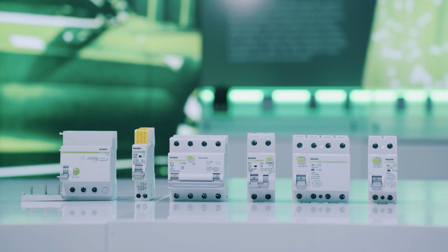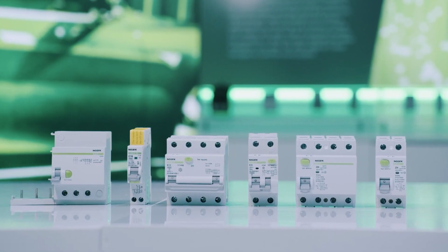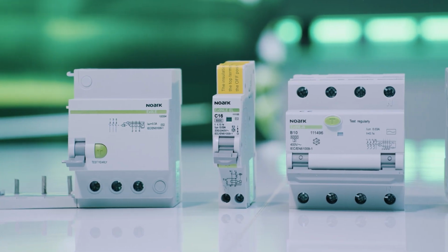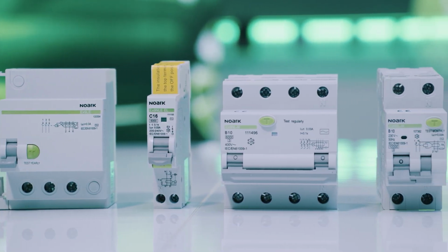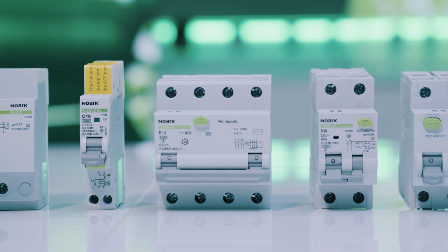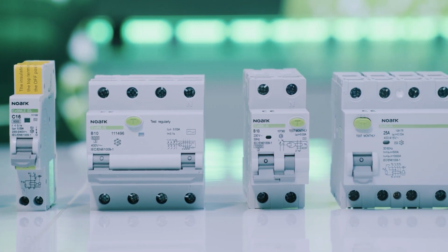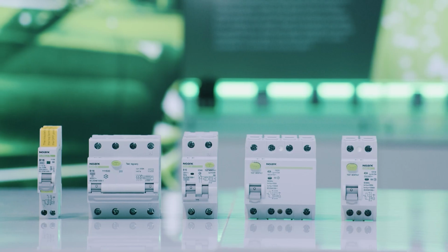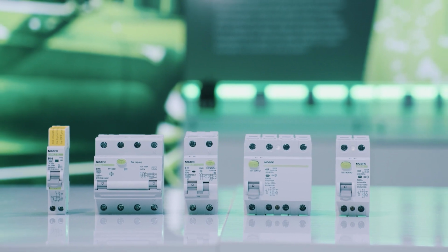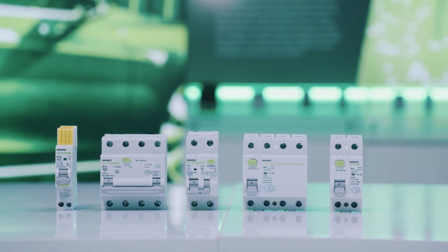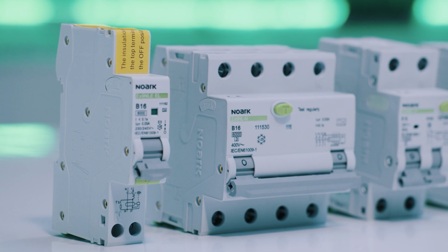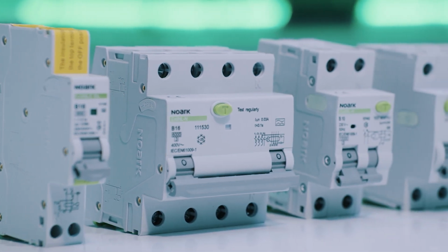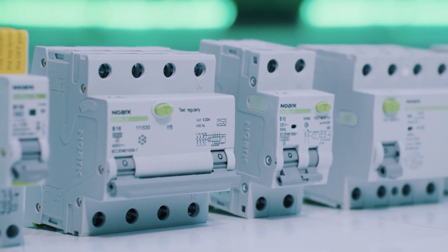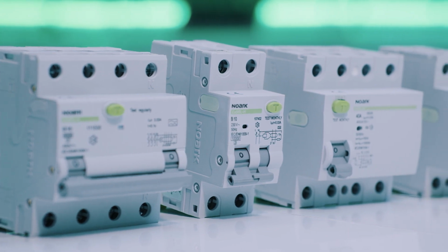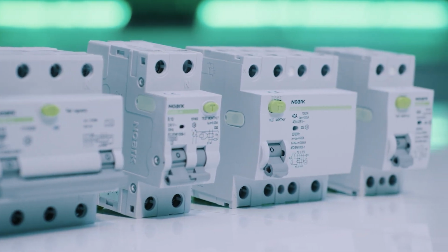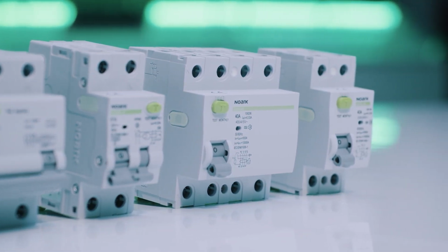The main parameter in the distribution is according to the types of currents which the device can react to. Type AC is sensitive to residual AC currents with nominal power distribution frequency. It's the most used type, which covers the vast majority of general applications used with heaters, boilers, lighting, etc. Type A is sensitive to residual AC currents and pulsating DC currents up to 6 mA. It is used in applications where pulsating DC currents can occur, and in some countries type A is the minimal requirement on the installations. Used with dishwashers, LED lightings, dryers, etc.